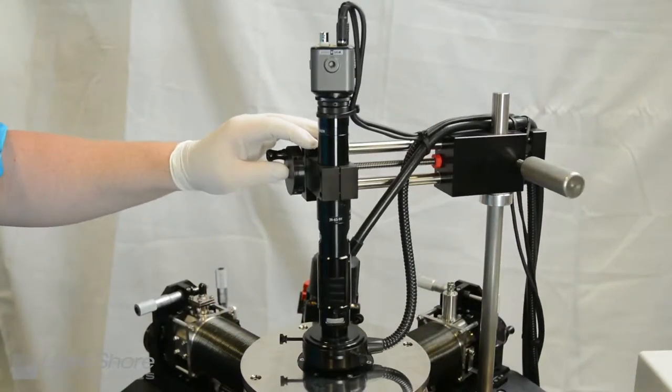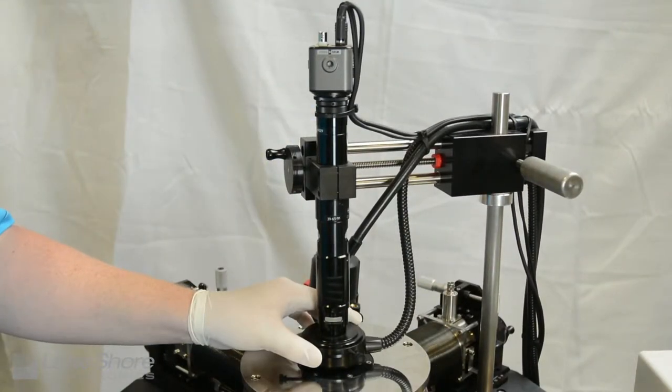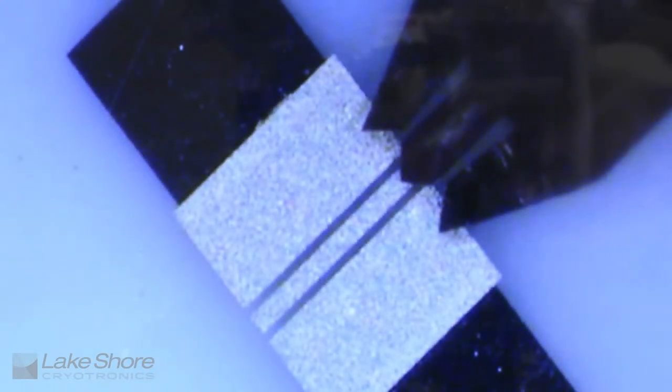Then we will swing the microscope back over the viewport and adjust the microscope to fill the monitor with the sample image and focus at the height of the sample landing pad.